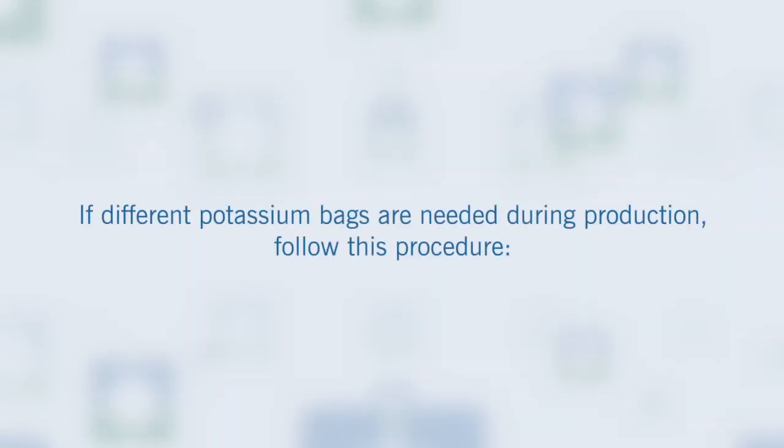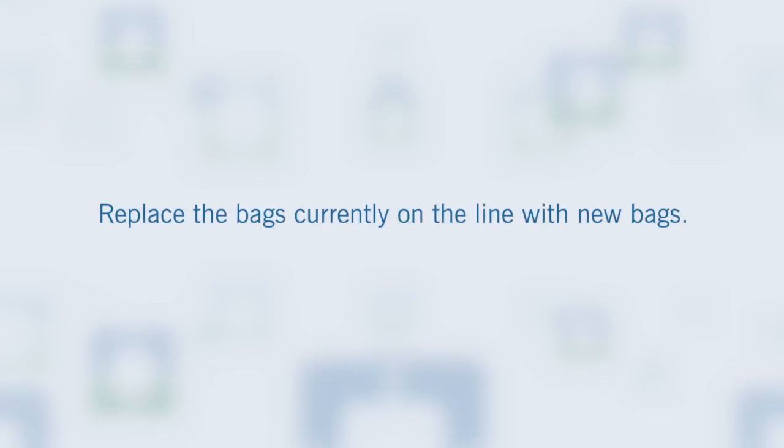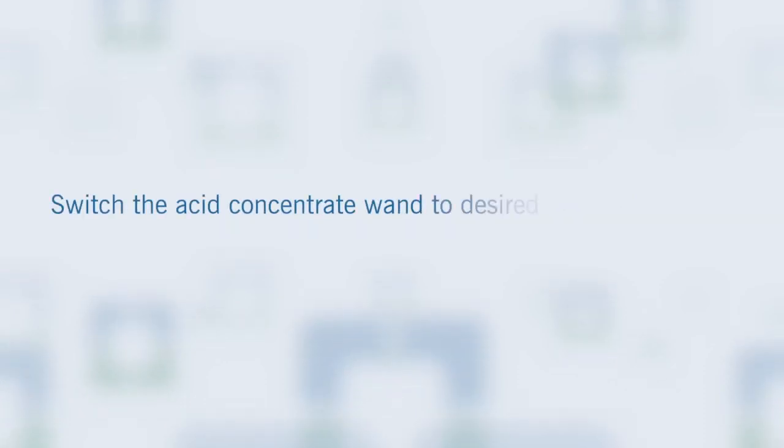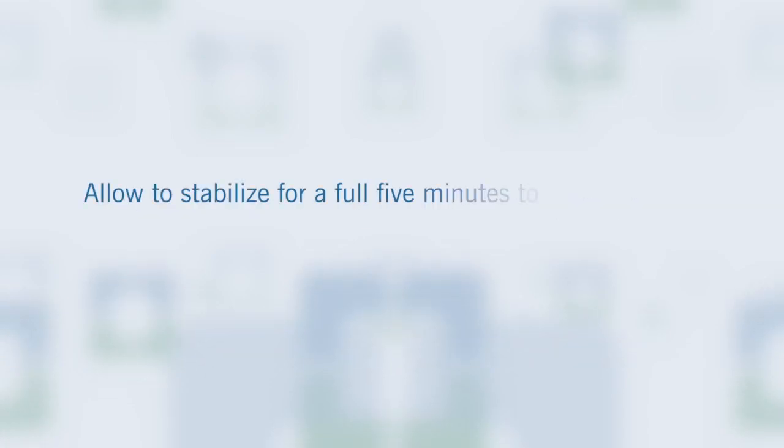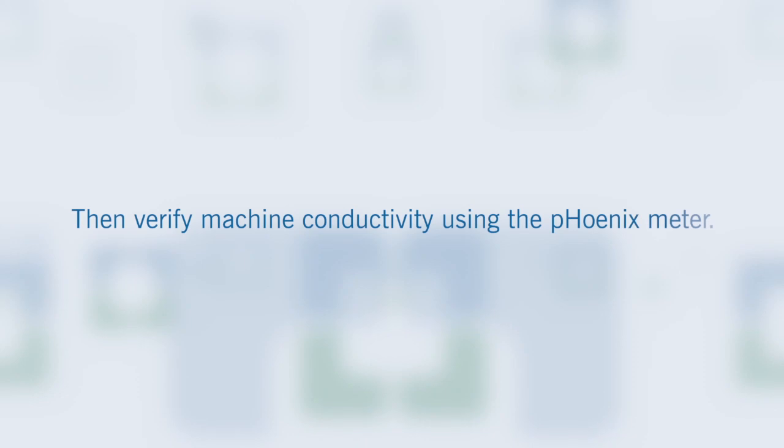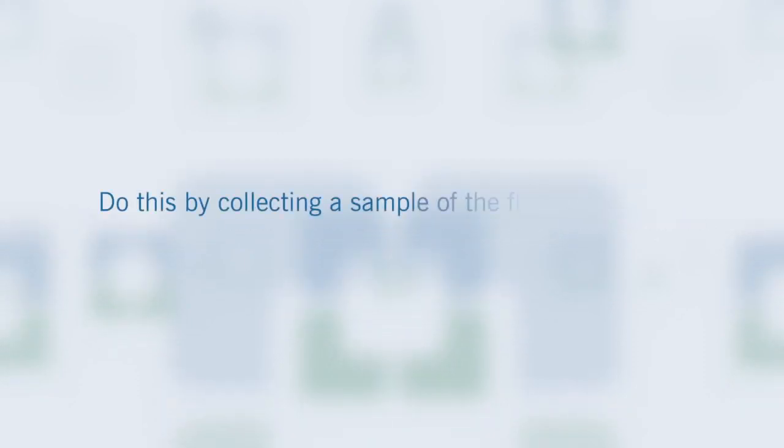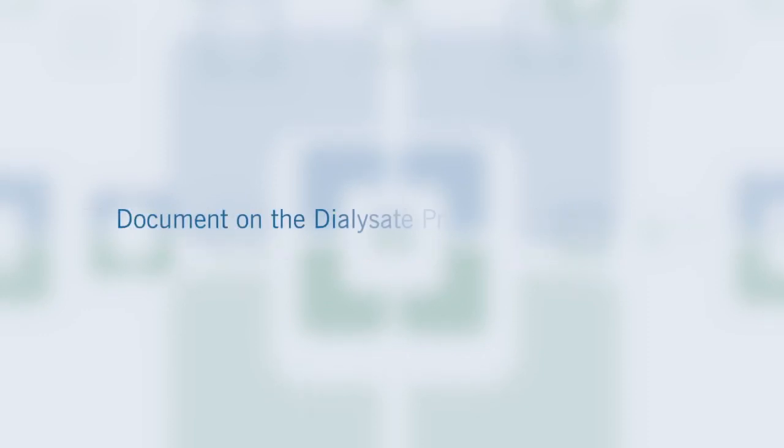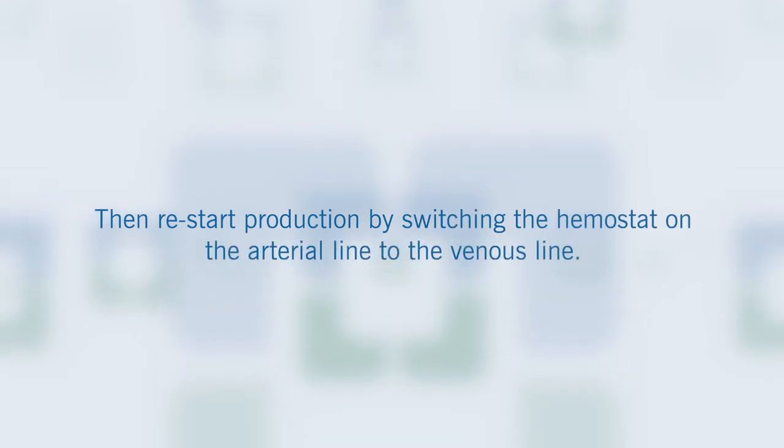Step 23: If different potassium bags are needed during production, follow this procedure. Place the hemostat on the arterial line. Replace the bags currently on the line with new bags. Put the machine into bypass mode. Switch the acid concentrate wand to desired acid concentrate. Place the machine back into normal operation. Allow to stabilize for a full 5 minutes to allow the new dialysate to flow through the system. Then verify machine conductivity using the Phoenix meter. Do this by collecting a sample of the fluid coming out of the venous line, then sample with the Phoenix meter and ensure the pH and conductivity are in the proper ranges. Document on the dialysate preparation log sheet. Then restart production by switching the hemostat on the arterial line to the venous line.